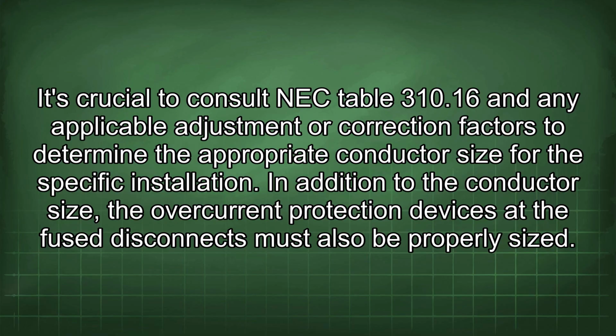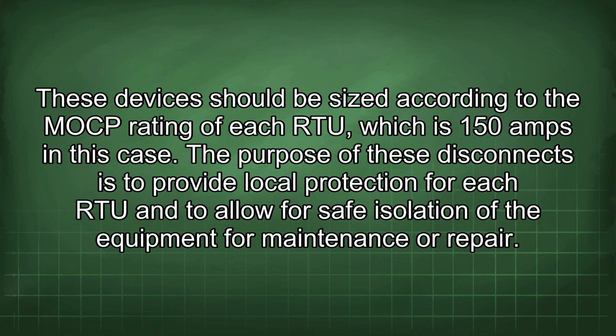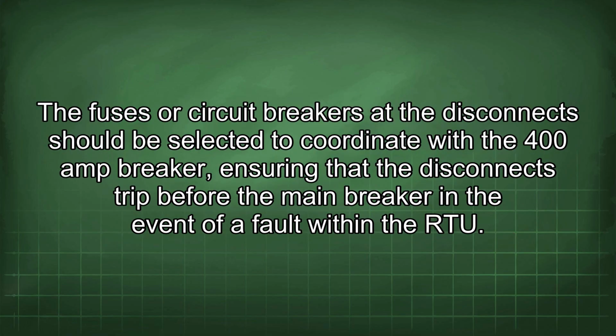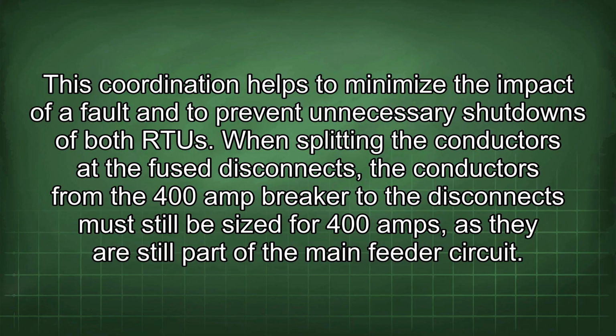for the specific installation. In addition to the conductor size, the overcurrent protection devices at the fuse disconnects must also be properly sized. These devices should be sized according to the MOP rating of each RTU, which is 150 amps in this case. The purpose of these disconnects is to provide local protection for each RTU and to allow for safe isolation of the equipment for maintenance or repair. The fuses or circuit breakers at the disconnect should be selected to coordinate with the 400 amp breaker, ensuring that the disconnects trip before the main breaker in the event of a fault within the RTU. This coordination helps to minimize the impact of a fault and to prevent unnecessary shutdowns of both RTU.